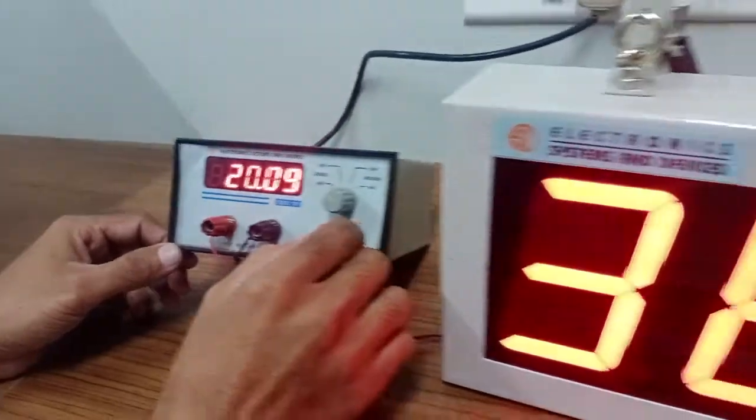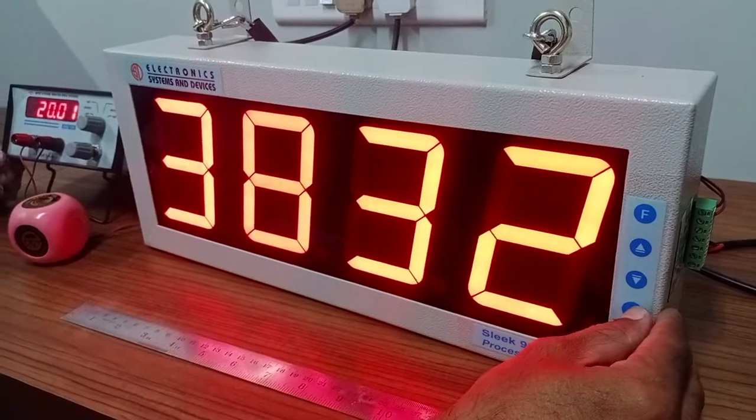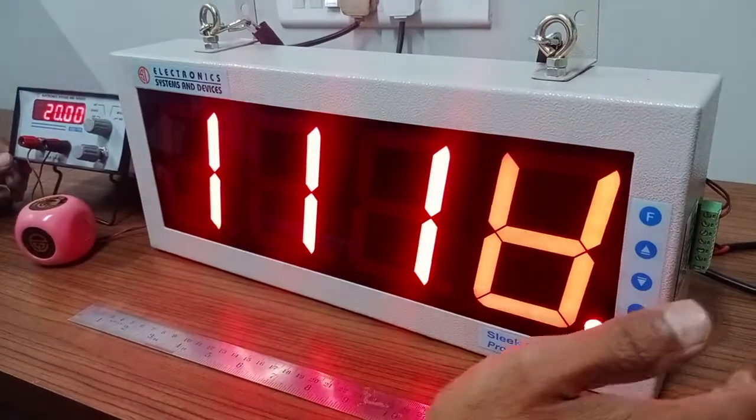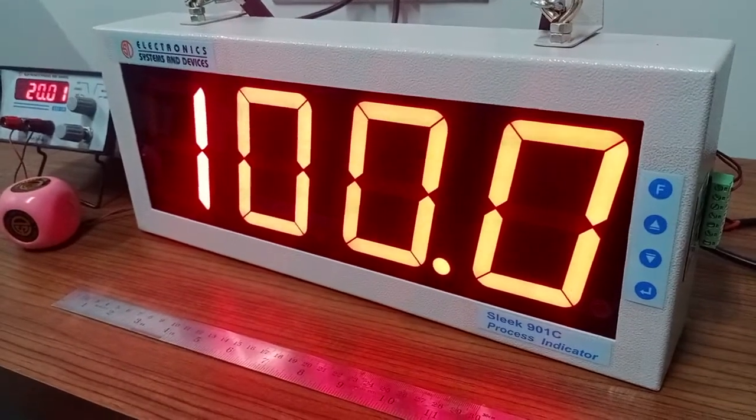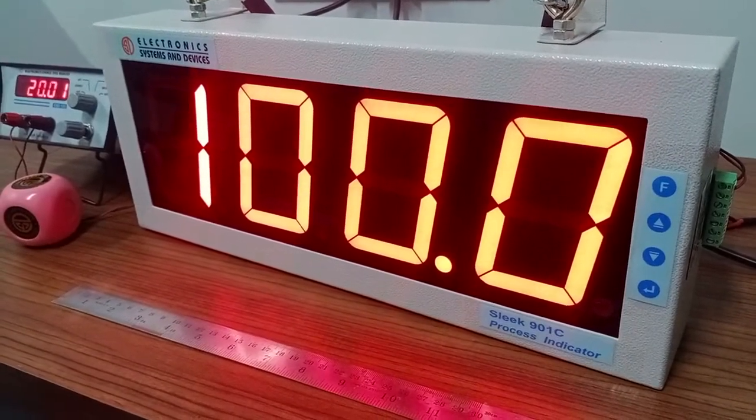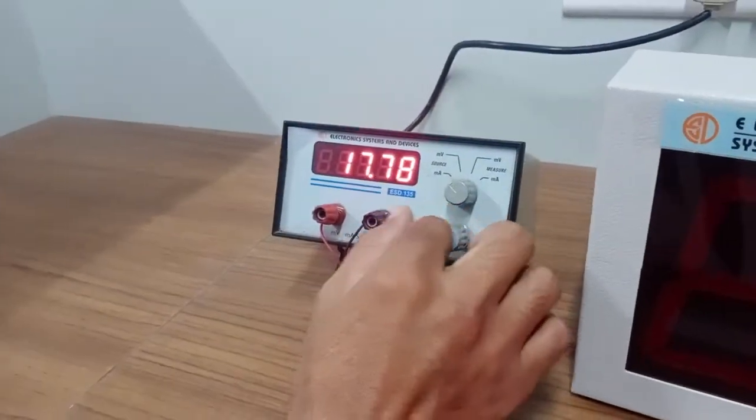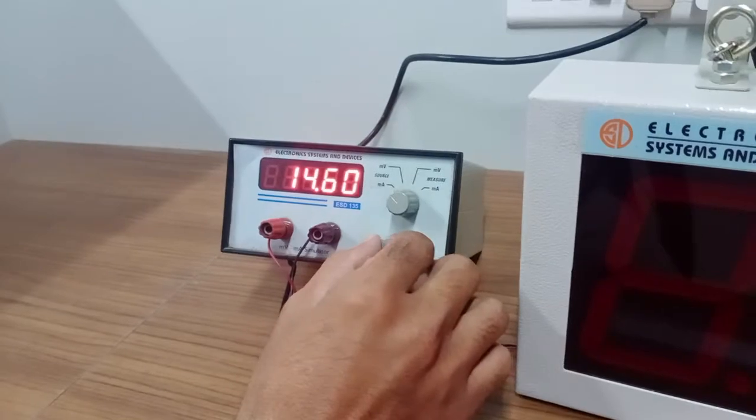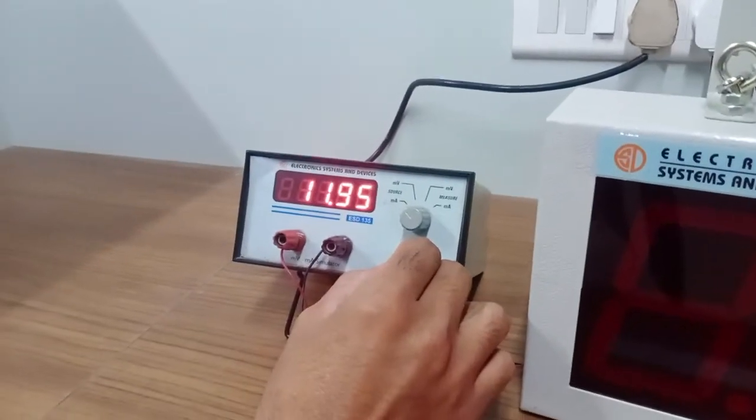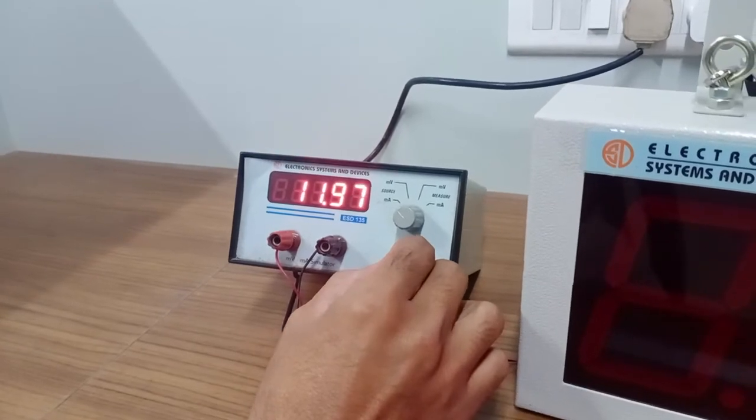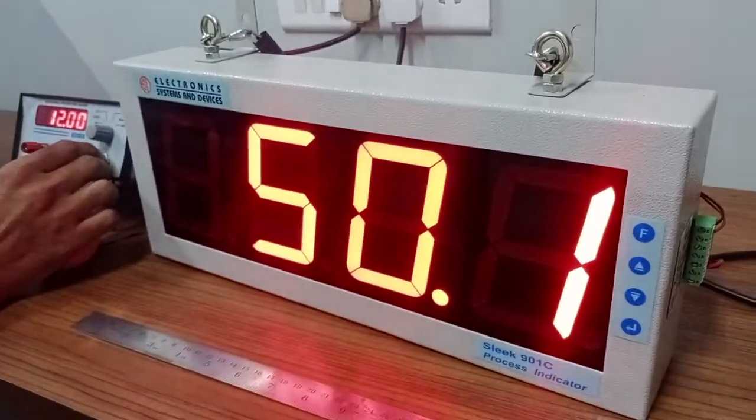And press enter. So now we are getting - you have entered upper limit as 100.0, so for the span we are getting the same. We'll just give a reading of 12 milliampere, and here we'll get a reading of 50. It is half, okay, that's fine.